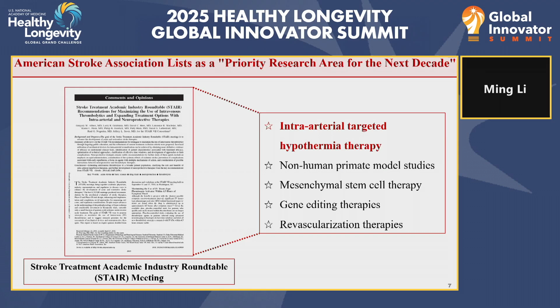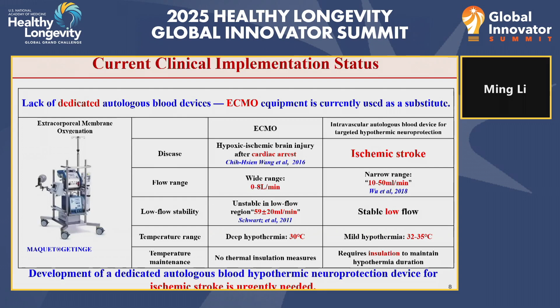Currently, autologous blood hypothermia technology used clinically mostly relies on ECMO equipment, which is primarily used for cardiac arrest patients, with a flow range of 0 to 8 liters per minute, unstable and low flow rate, and catheter lack of insulation during cooling. Our device is specially designed for ischemic stroke patients with a flow range of 10 to 50 milliliters per minute. Stable flow rate is in the low flow range, enabling local brain tissues to be made hypothermal.